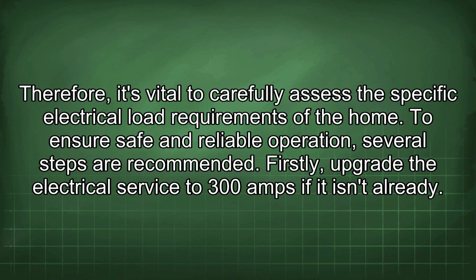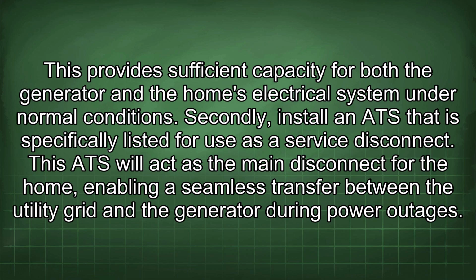To ensure safe and reliable operation, several steps are recommended. Firstly, upgrade the electrical service to 300 amps if it isn't already. This provides sufficient capacity for both the generator and the home's electrical system under normal conditions. Secondly, install an ATS that is specifically listed for use as a service disconnect. This ATS will act as the main disconnect for the home, enabling a seamless transfer between the utility grid and the generator during power outages.